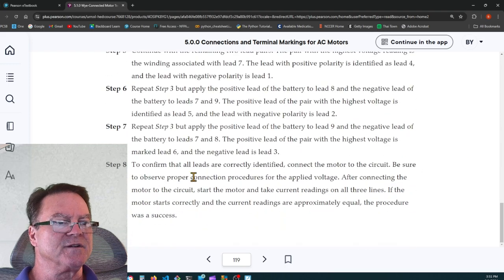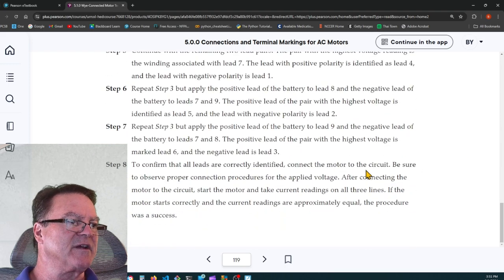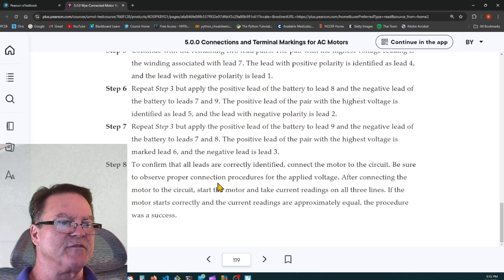All right. To confirm that all leads are correctly identified, connect the motor to the circuit. Be sure to observe proper connection procedures for the applied voltage. After connecting the motor to the circuit, start the motor and take current readings on all three lines. If the motor starts correctly and the current readings are approximately equal, the procedure was a success.